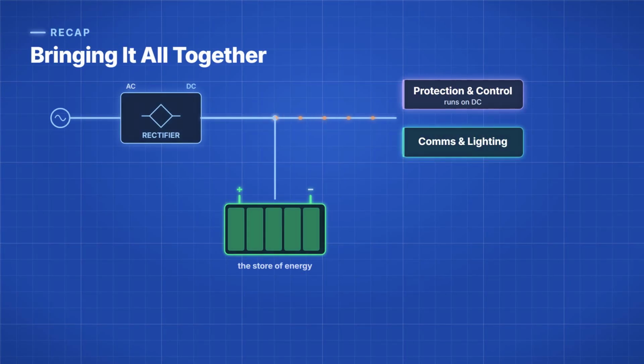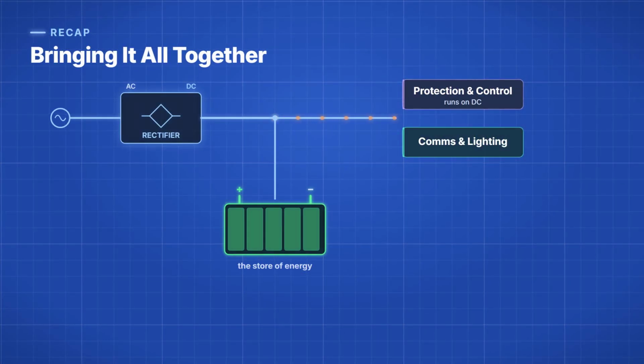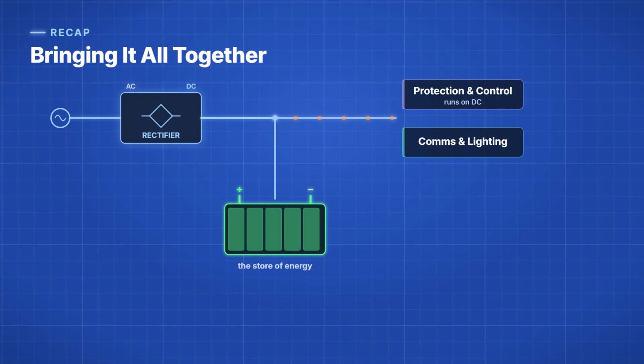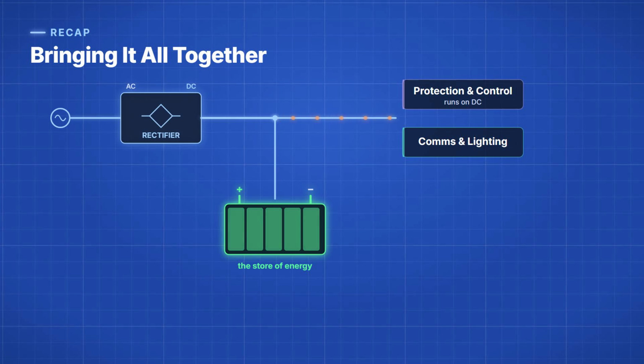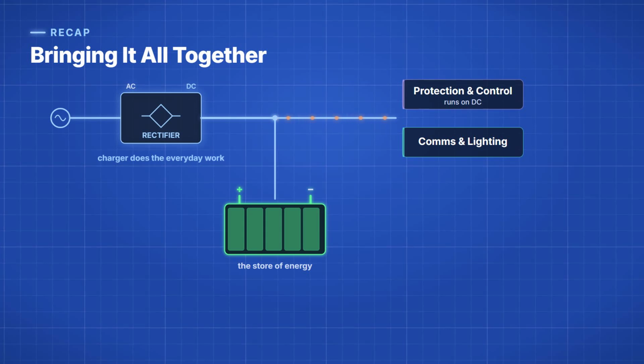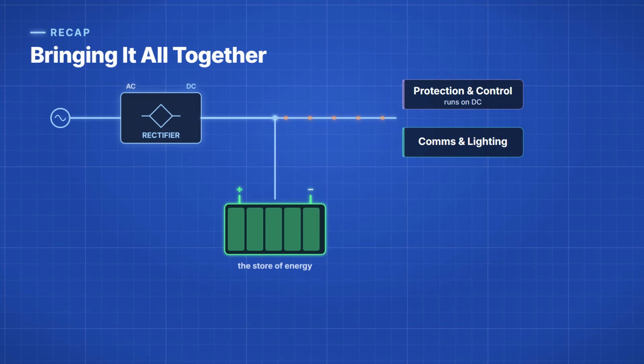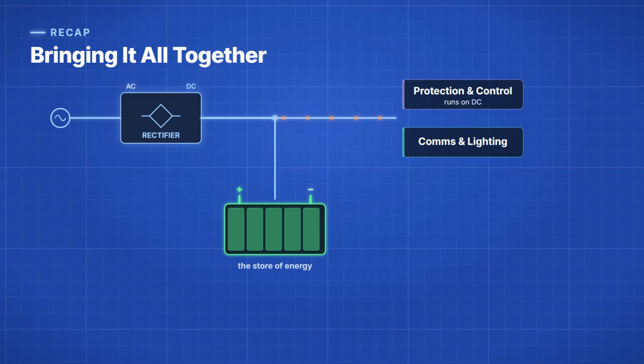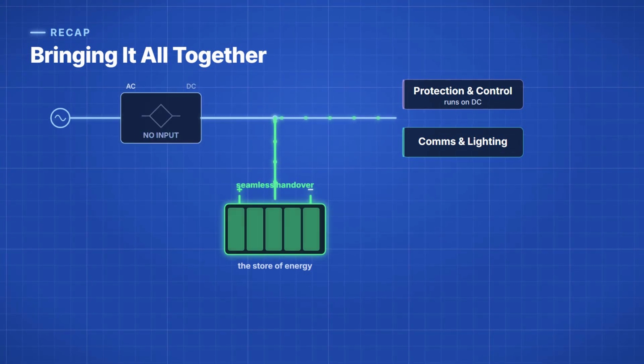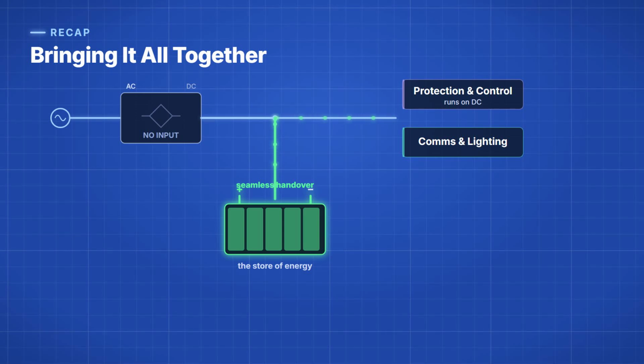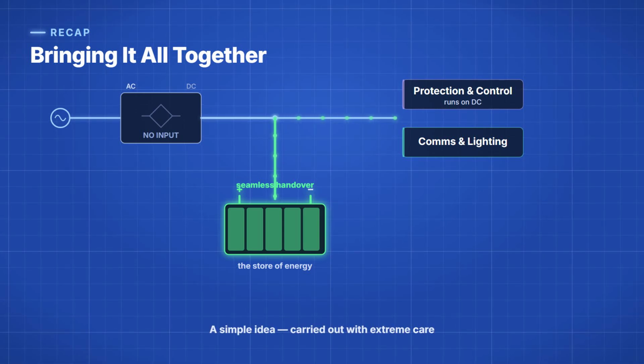So let's bring it all together. A substation runs its protection and control on DC because that power has to be there even when the grid is not. The battery bank is a store of that energy, sitting at a steady voltage on the DC bus. A charger does the everyday work and keeps the battery full, and the instant the supply fails, the battery takes over with no gap and no interruption, so the breakers can still trip. And the substation can still protect itself. It's a simple idea. It's carried out with extreme care, and it's working quietly right now under every substation on the grid.